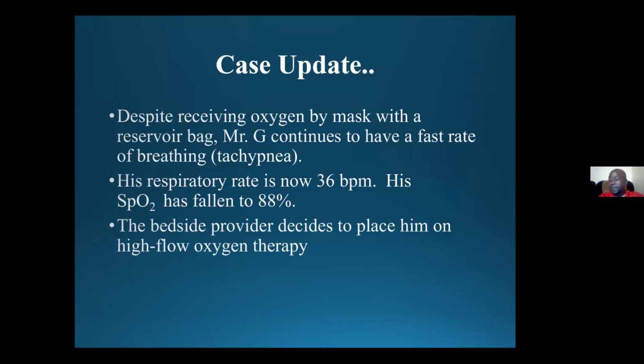The other thing, for the people who have the high flow oxygen therapy device, like people here in some COVID centers, is that on that device there are two types of parameters you have to set: the flow rate and the FiO2. As the video showed, the FiO2 can be set from 21 to 100%, and the flow rate from 20 to 35 liters per minute. So you adjust your FiO2 according to the need to meet your target in terms of oxygenation. When you meet your target, you can de-escalate to low flow when your need is less than 50% FiO2, or less than 20 liters per minute of high flow nasal cannula.